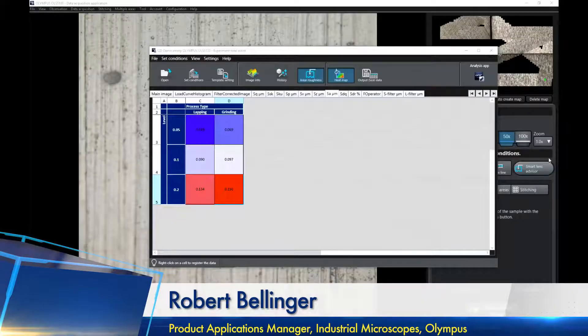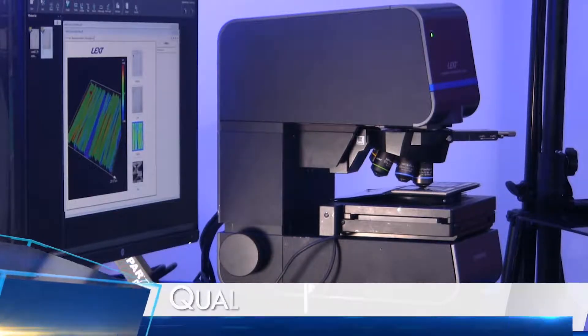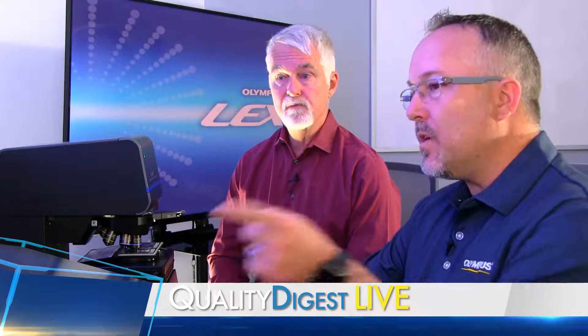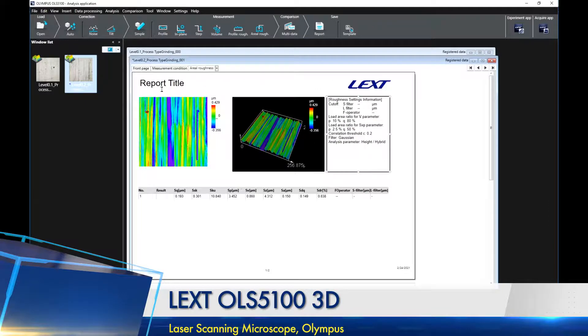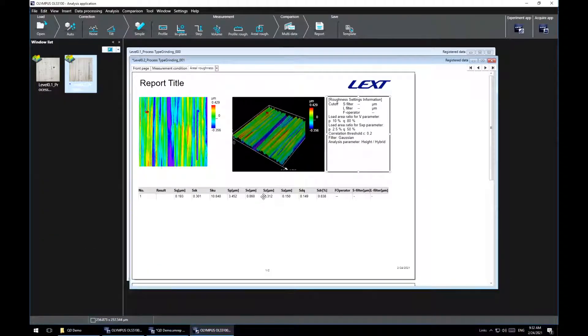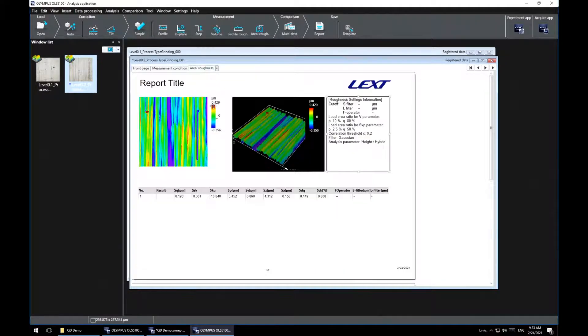That's another really good benefit to the Smart Experiment Manager. If you want to go back and re-look at any original images, you can open them right from the experiment manager — right-click on the image, select Open with Analysis App, and it takes you right to the analysis software showing the individual image. You can render it, see value results, see what your measurement conditions were, look at the overall image, and do more measurements from there.